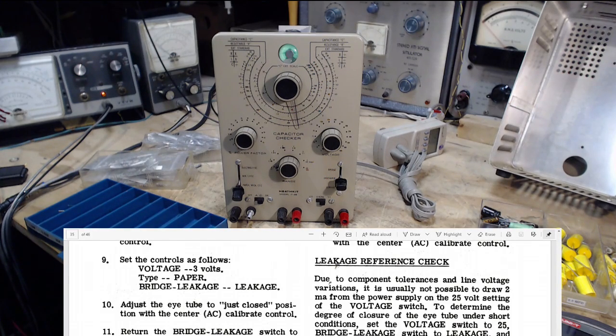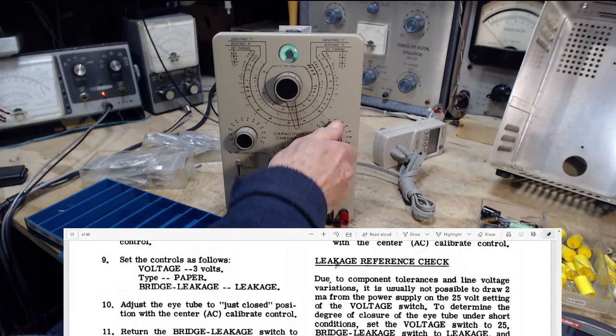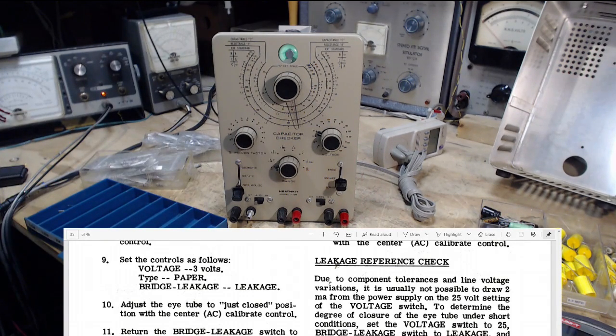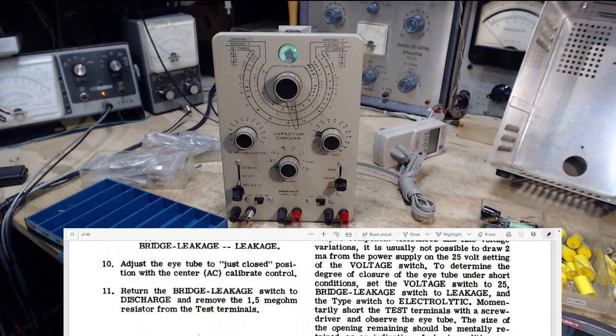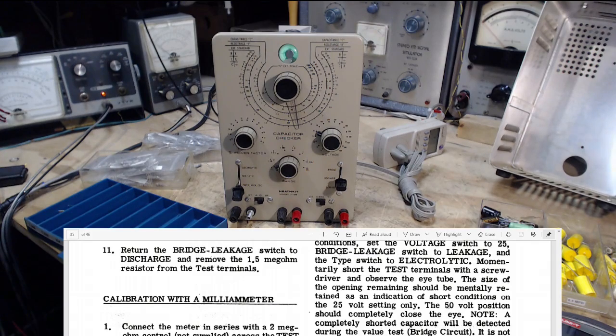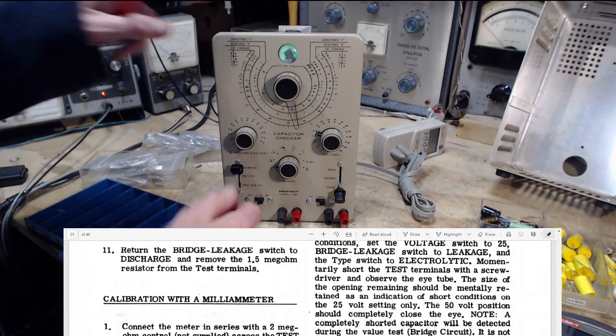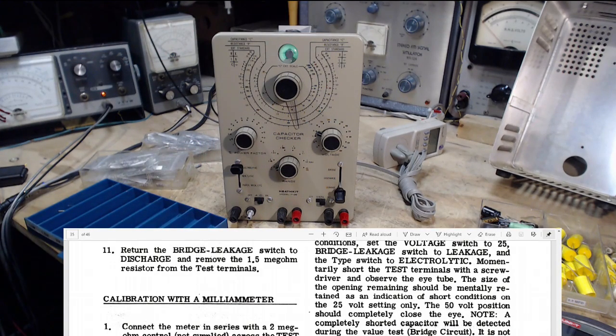Okay, set the voltage switch to 25. Bridge leakage switch to leakage. And type switch to electrolytic. Momentarily short the test terminal with a screwdriver and observe the eye tube. The size of the opening remaining should be mentally retained as an indication of short conditions on the 25 volt setting only.